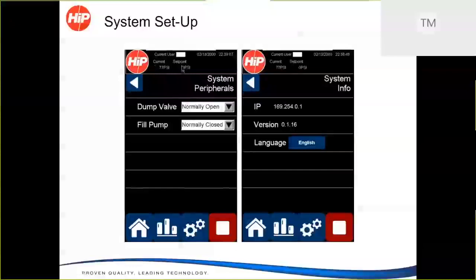The last thing I want to touch on in setup is that we do have the ability to control a dump valve or a fill pump on the system. If you want to speed up your system, these are on-off air type controls. You're going to run an air solenoid that will turn the signal on and off to run either a pump or a pneumatically actuated valve that you could use for bleeding off pressure on your system or controlling a fill pump. So for example, you could say, I want to turn on a fill pump, run a low pressure pump and fill up a very large volume. Then when that volume is done, it'll shut the fill pump off and turn on your pressure pump and do the pressure test.